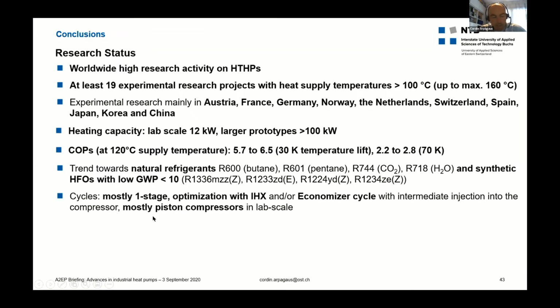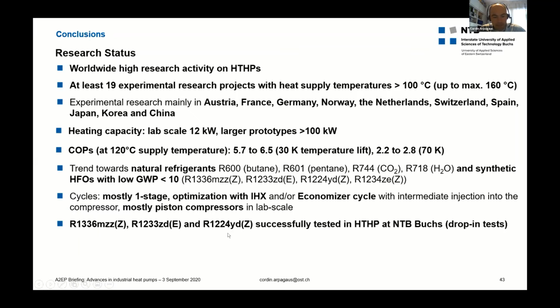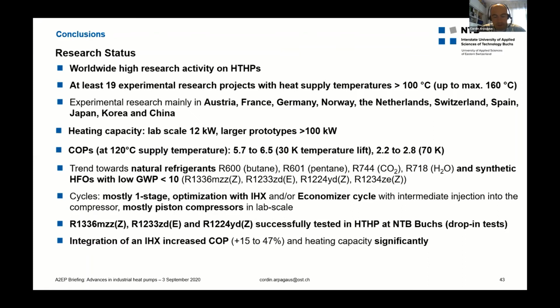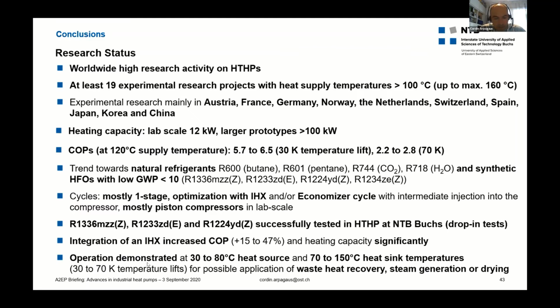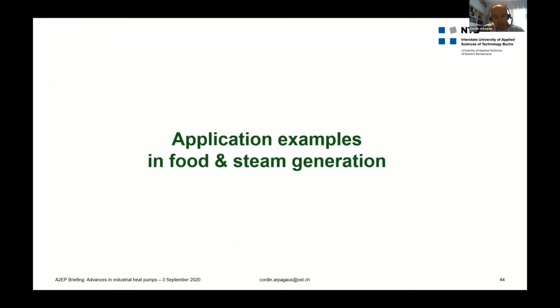The heat pump cycles used are mainly one stage, but they can also be optimized with internal heat exchanger designs, economizer cycles, and so on. Mostly piston compressors are used in lab scale. And in our university, in our system, we tested hydrofluoroolefins, and we also increased the COP by including the internal heat exchanger. So it's an important component, I think, to design heat pumps. And we could also demonstrate typical applications which would be useful for industry, like waste heat recovery, steam generation or drying. So these are the major applications. Now, some application examples.